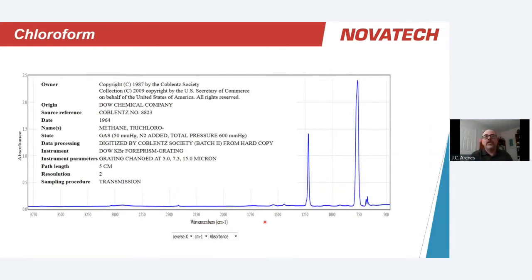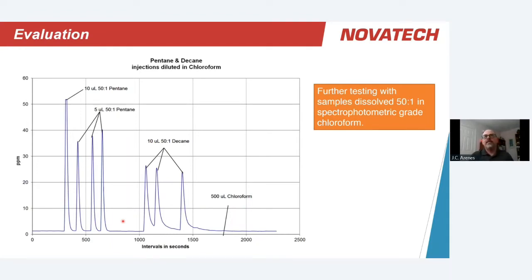We then chose chloroform as the dissolving agent rather than methyl ethyl ketone. Chloroform's infrared absorption is completely away from where our hydrocarbons absorb, ensuring the background solvent would not influence the reading. Testing with pentane and decane diluted in chloroform showed excellent response — even 10 microliters at 50-to-1 dilution for decane. When we injected 500 microliters of straight chloroform, there was no response whatsoever, confirming that chloroform had no influence on the reading and that we were still getting excellent response from C5 through C10 hydrocarbons at 50-to-1 dilutions.